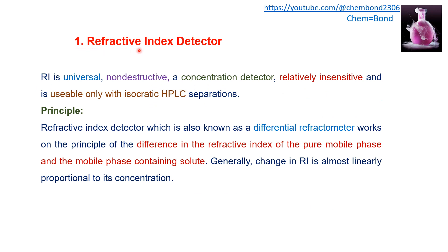The first bulk property detector is the refractive index detector. It is a universal, non-destructive concentration detector that is relatively insensitive and usable only with isocratic HPLC separation. The basic principle of the refractive index detector, also known as a differential refractometer, is the difference in the refractive index of the pure mobile phase versus the mobile phase containing the solute. Generally, the change in refractive index is almost linearly proportional to the concentration of the solute in the mixture.